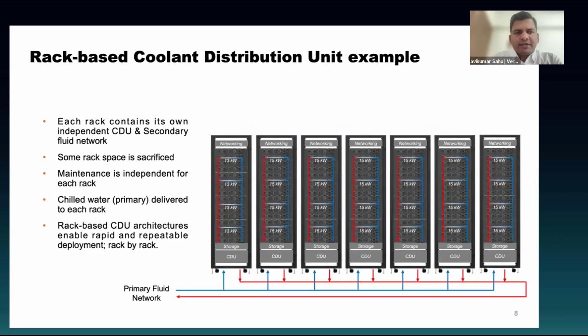This is also one of the configurations, rack based. Here, for each and every rack you can have one CDU. So this is called indoor CDUs. This can be beneficial when, let's say, you are going to have 2 or 3 racks to be liquid cooled, and it can be very useful when you are transitioning from air cooled data centers to liquid cooled. So this may be very small, easy, and can be retrofit easily into your conventional data centers.